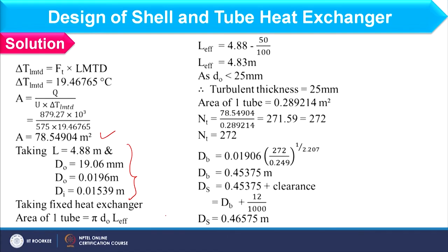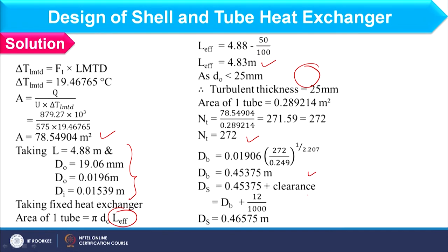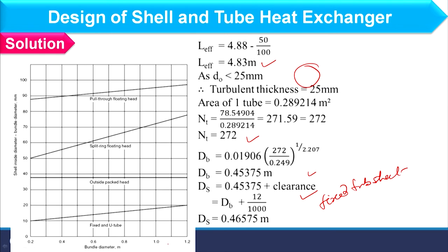Next, we find the bundle diameter. For one tube pass, K1 and N1 values are taken from the table, and based on these values, the bundle diameter comes as 0.45375 m. Since the maximum temperature is 60°C, we should use a fixed tube sheet. Using the clearance graph and adding the clearance to the bundle diameter, we obtain the shell diameter as 0.465 m.